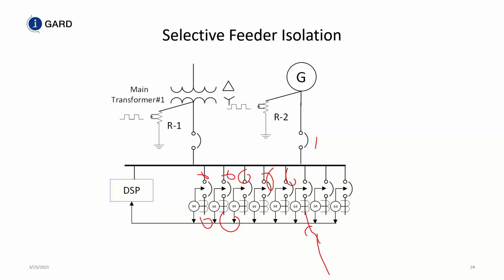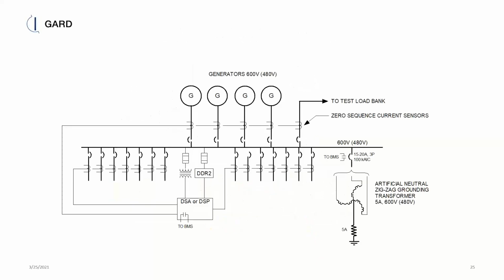And so my competition likes to put out these flyers that say they have trending and historical events and logging, but really all they're going to log is they have a fault, they don't have a fault. The fault is back, the fault is gone. With my system, I tell you, you have a fault, the fault is on feeder number 6. You have a fault, the fault is on feeder number 5. So it gives you more information about what to do when you have that fault on the system. With generators, say for example, we've had some instances when we had many generators on a synchronizing bus.